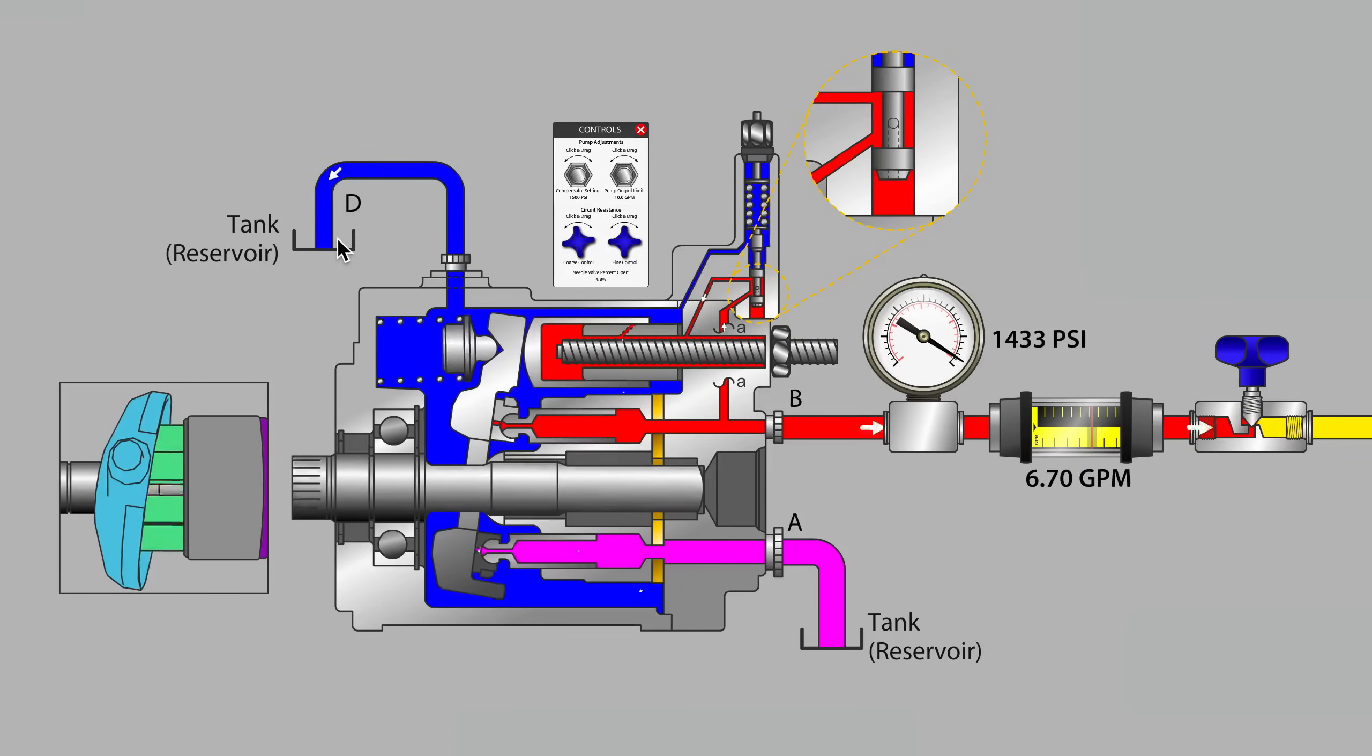Manufacturers recommend a maximum amount of back pressure present on this line, meaning let's not see this line get too narrow in diameter. It's important not to have a filter that could cause blockage on the case drain line.